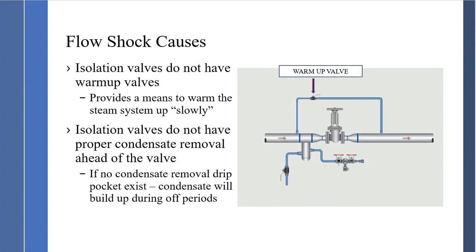Flow shock is dangerous and one to avoid. When installing an isolation valve three inches or larger, you must always have a smaller bypass valve called a warm-up valve. This allows gradual warm-up of the steam system and prevents flow shock. You cannot simply open a large eight-inch valve slowly to warm up a steam system effectively.